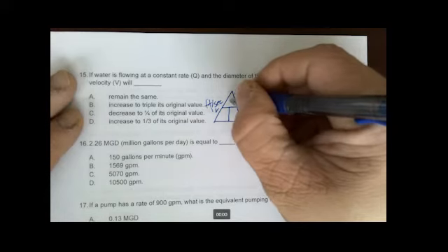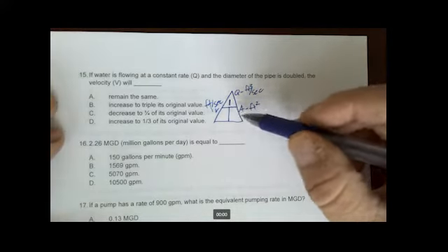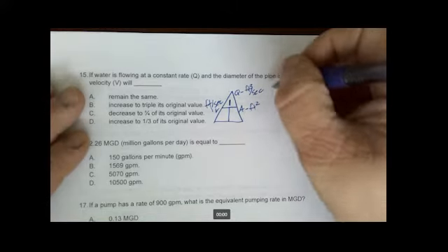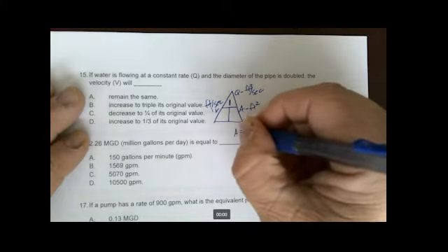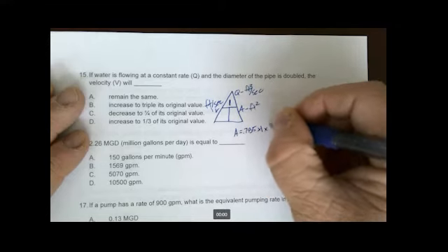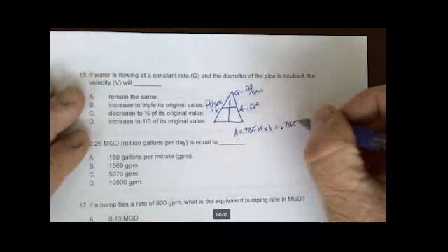So we're going to assume the flow rate is 1. It doesn't change. I like to call this the rule of 1. So we need to figure out what the area would be if the diameter was, let's say, 1 foot. The area for a continuity equation is always 0.785 times the diameter times the diameter. We're assuming 1 foot, so this gives me an area of 0.785.